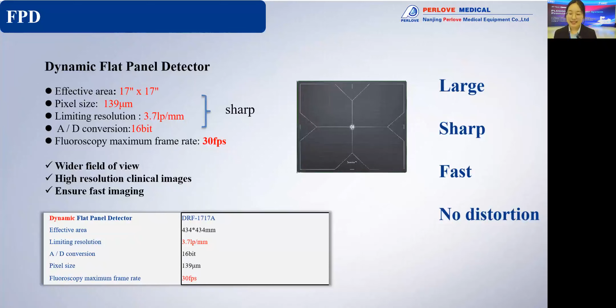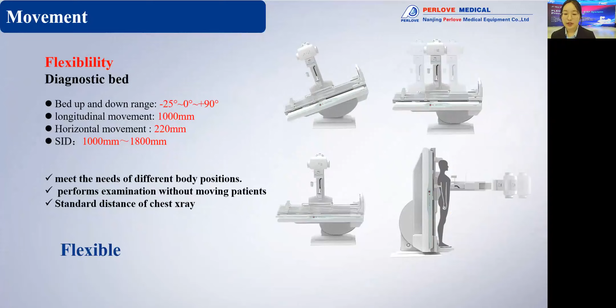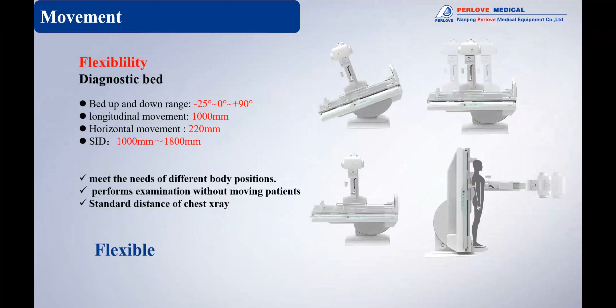Okay, after our flat panel detector, I'd like to introduce our movement. Flexibility is the best adjective to describe our movement. Look at its diagnostic bed. Our bed up and down range can be from -25 degrees to 90 degrees, which means it can meet your needs for different body positions. The second parameter, our longitudinal movement, can reach 1,000 millimeters. Our horizontal movement can reach 220 millimeters, which means it can perform examinations without moving our patients, so it can avoid secondary injuries to our patients. Look at its SID. Its range is from 1 to 1.8 meters, which is the standard distance for chest X-ray. Okay.